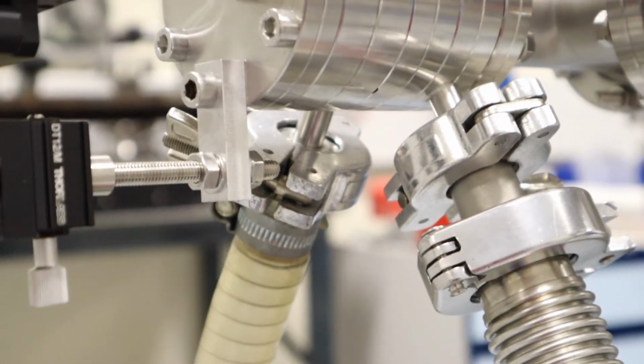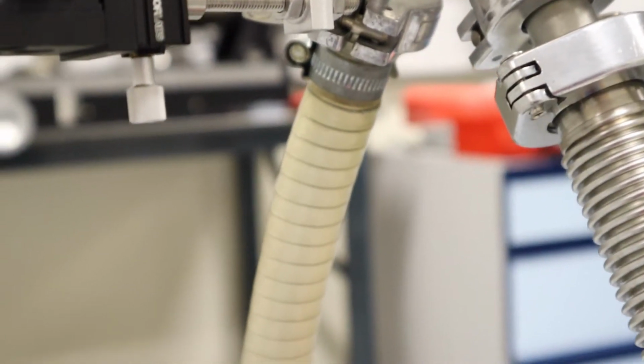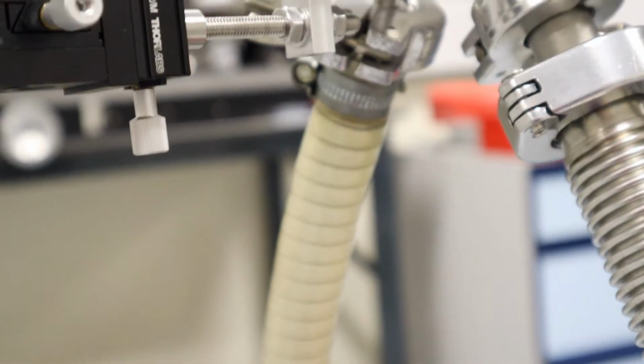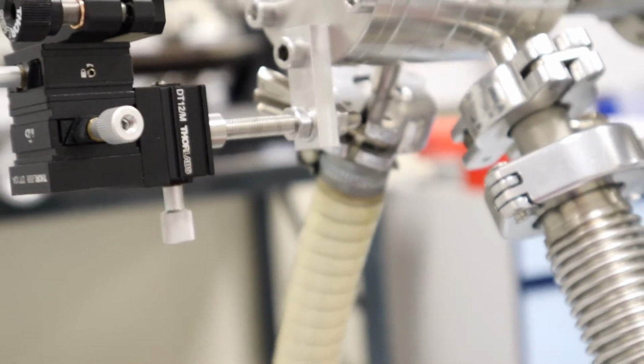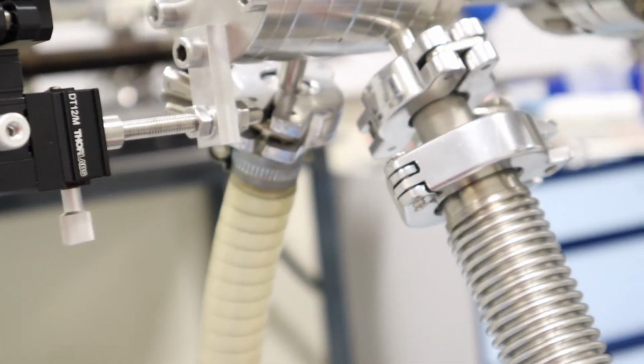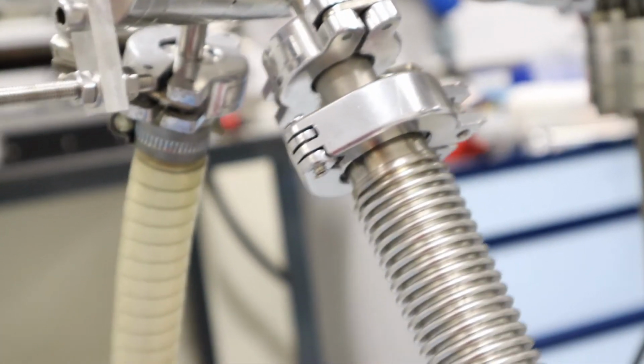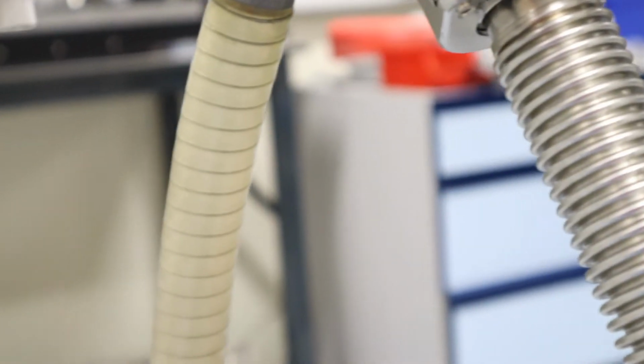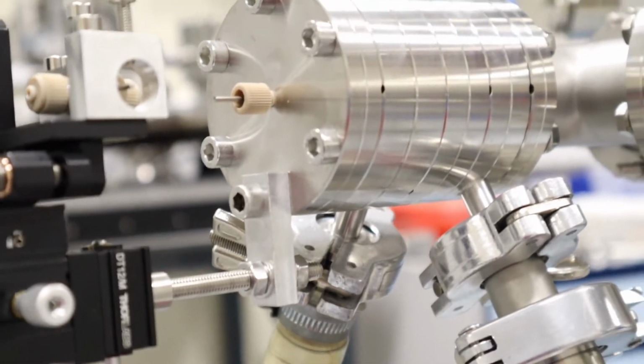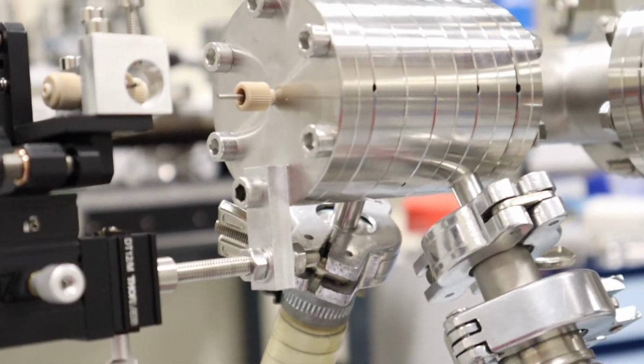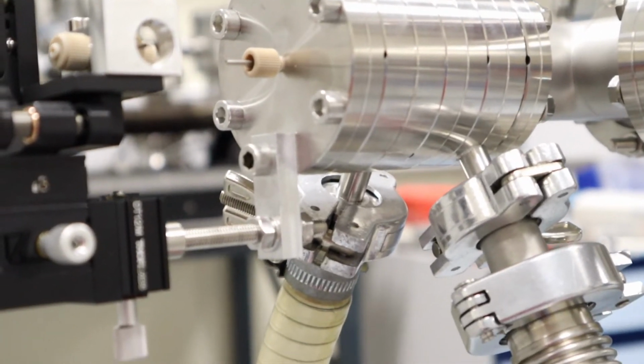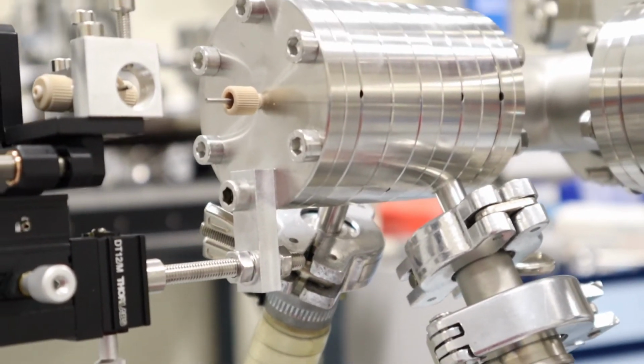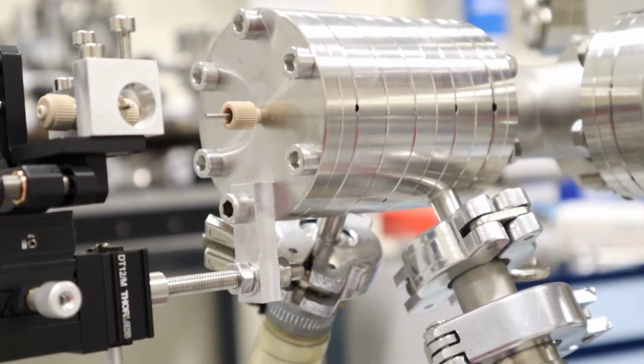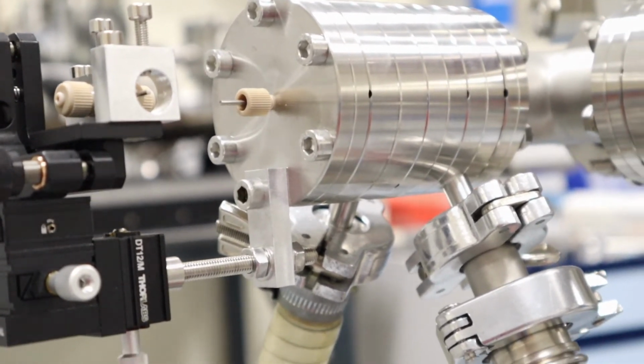So now both stages are connected, and there's no significance to the fact that the scroll pump attached to stage 1 is a polymer tube rather than a steel bellows. It's just what was available. So I'll go ahead and start the pumps, and while it's pumping down we can attach some of the other ancillaries.